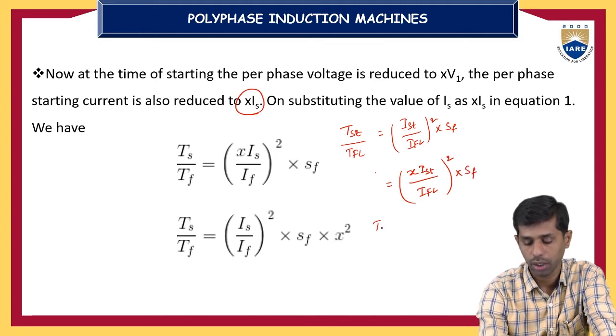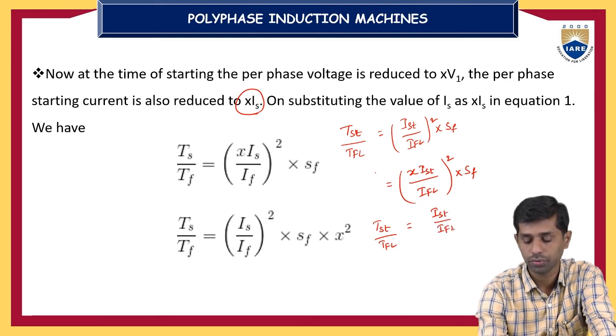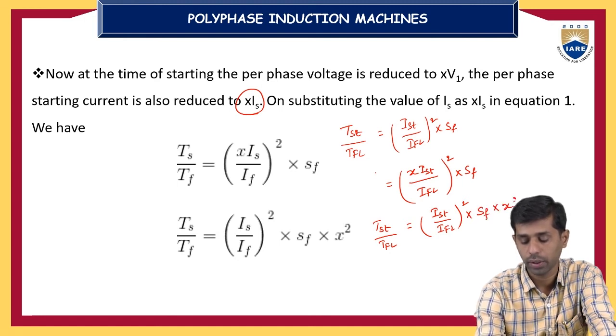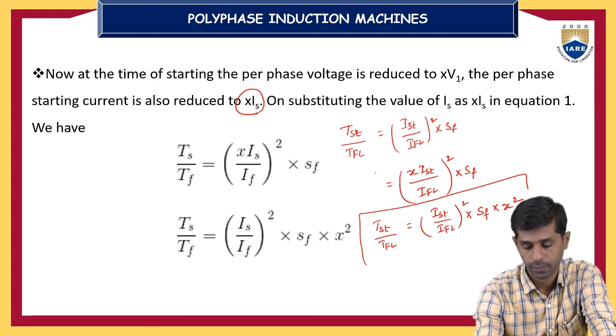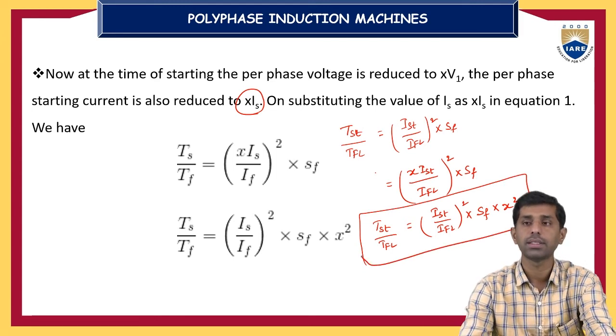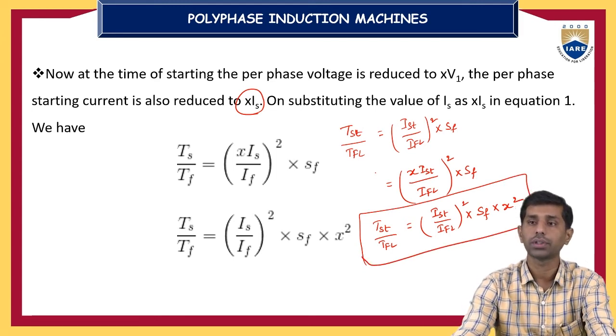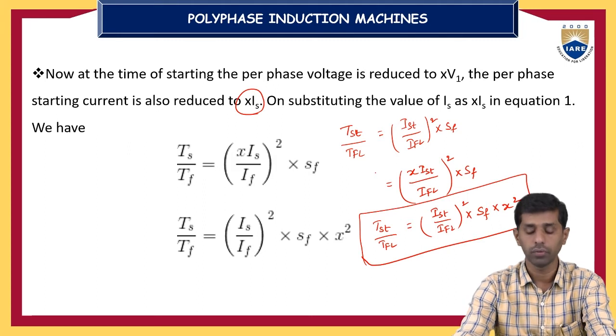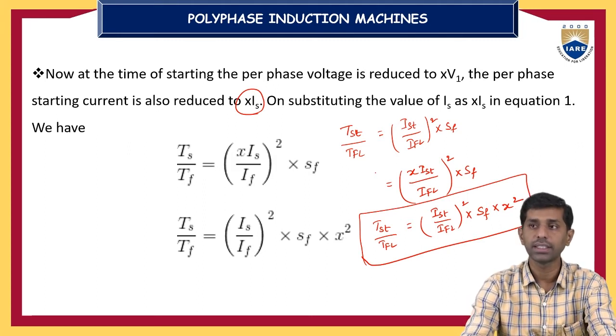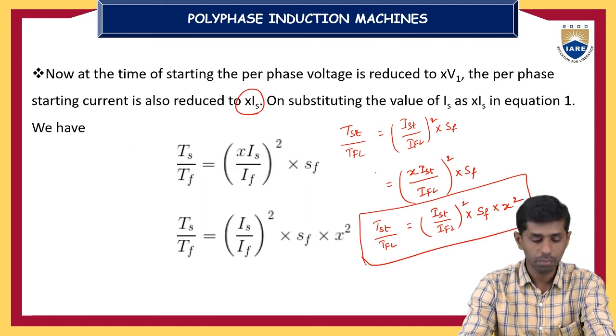So we can write the expression. T_ST by T_FL, the ratio of starting torque to full load torque, is equal to (I_ST by I_FL) square times the slip at full load condition into x square. And this is the expression for the ratio of starting torque to full load torque when we go with the resistor starting method. But this method is...